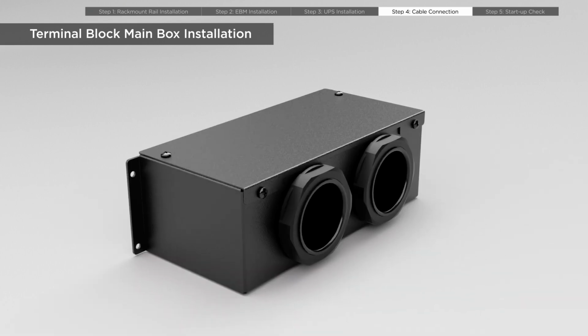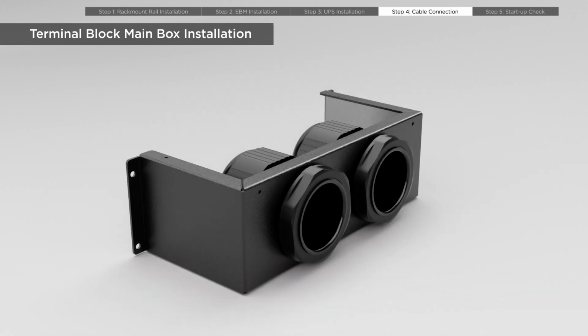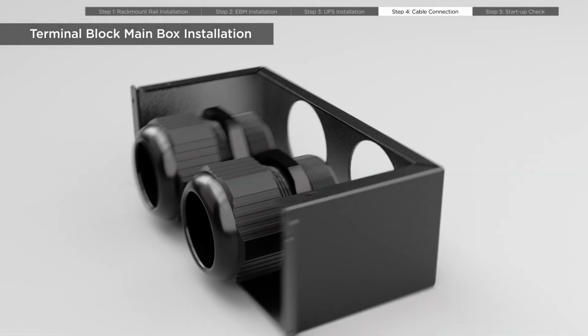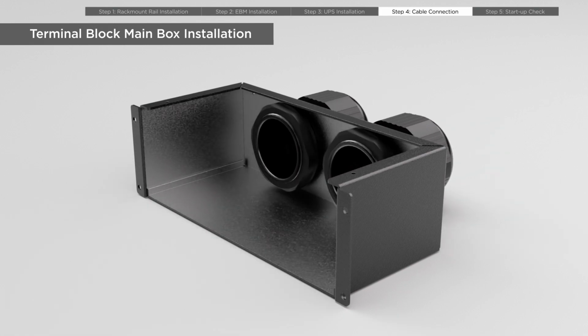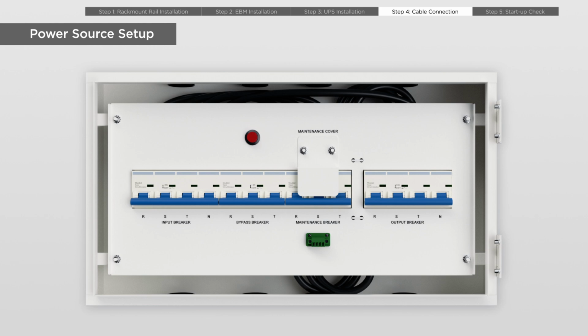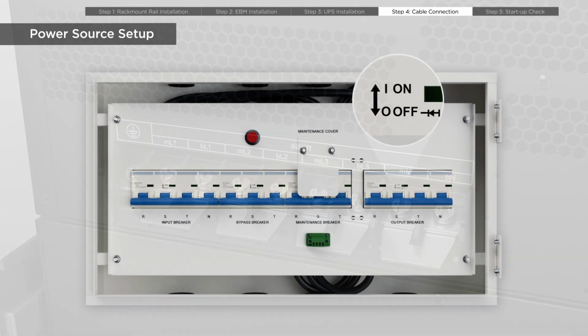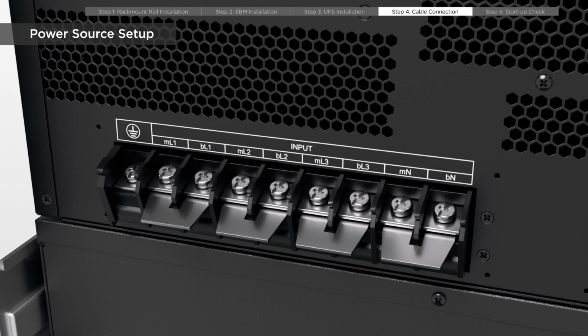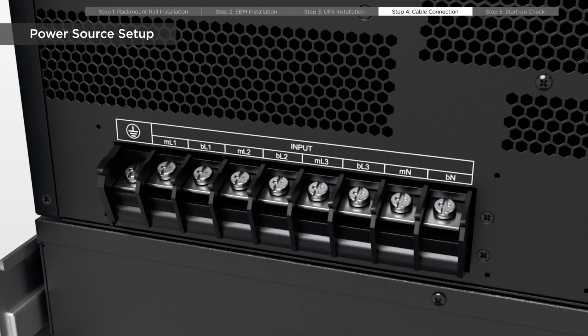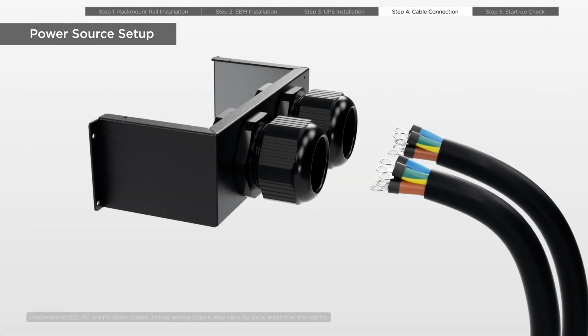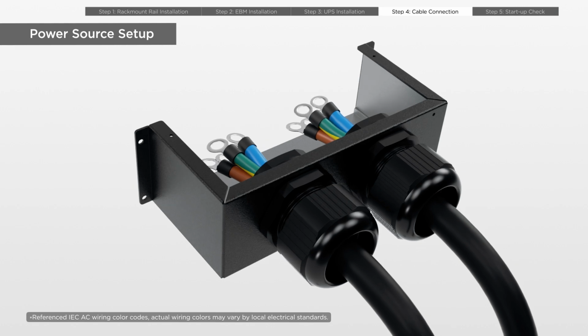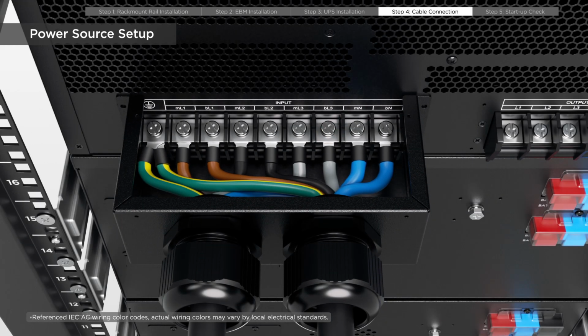Remove the terminal block cover by loosening 4 screws, then loosen and reattach the cable glands. All circuit breakers must be off before connecting cables. Remove the copper sheets for dual input power setup. Route the power cables through the cable glands and verify that the phase sequence matches the UPS terminal labeling.